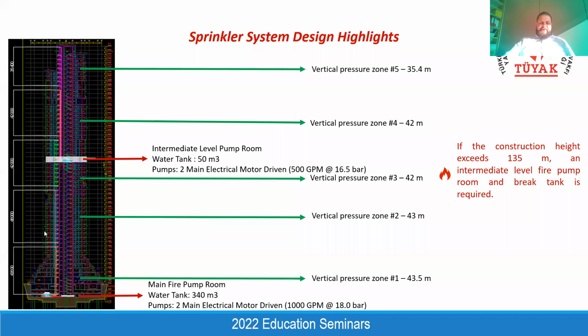That's why after having 3 vertical pressure zones, we provided an intermediate level of pump, and the upper levels are fed by this intermediate level of fire pump. If you are not taking this detail into account during your design, the mechanical designer comes into the project.